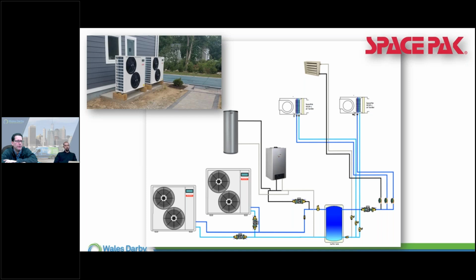And how about meeting requirements for NEEP? Obviously we're grandfathered in on the DX side. On the water side, that's what I was saying earlier, a lot of the utilities and the NEEP program just don't recognize air to water units. We kind of fall underneath the air source heat pump category, it's an air source heat pump hands down, but it's a different media. Even AHRI's directory doesn't have a category for air to water, they have ground source. We don't fit into that because we're a closed loop inside, there's nothing in the ground or anything like that.